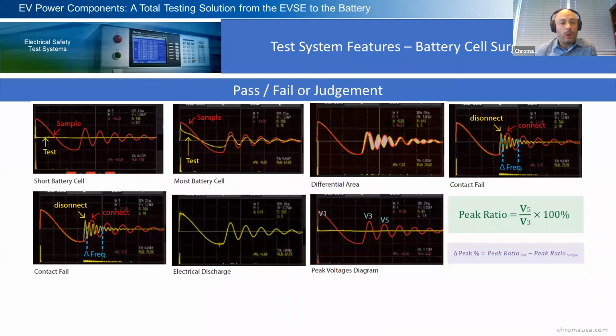Now, we have a pass-fail or judgment type test here. We have 8 different types of tests for the battery cell surge. One is the area, which basically compares the total area between the actual pulse waveform and the sample waveform, right? The next one is the differential area, again the area created between the test waveform and the sample waveform. So you're going to have a golden waveform for a known good unit. That's going to be your template, and then you're going to compare it to the actual test waveform.